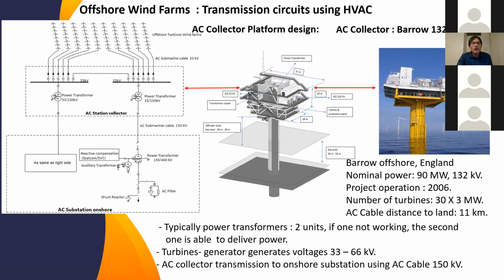Offshore connection here is through AC. Imagine an offshore cluster of wind turbines. The offshore wind turbines will be connected to an AC collector station located offshore. From the AC collector substation, the power transformer will step up the voltage, because the voltage we produce here is maybe medium voltage, somewhere around 33 kV. We increase it using the power transformer in the AC collector station to a higher voltage, and then from the AC collector we transmit using AC submarine cable at 150 kV to the onshore substation.